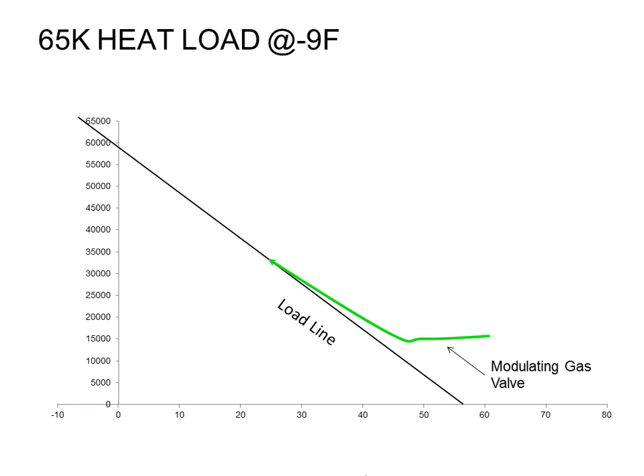It'd be much better if I can provide you a consistent, whatever, 100, 105, 110 degree air all the time, blowing continuously out of your registers, and never have to cycle that thing off. That's what a modulating furnace is going to be able to do for you. It's going to ramp up and down to match exactly how much heat you need and always give you heat out of the register.